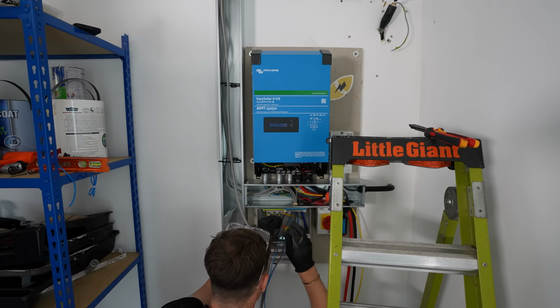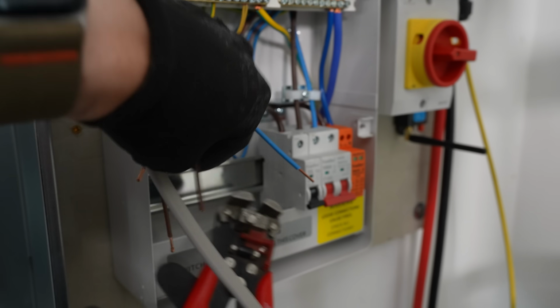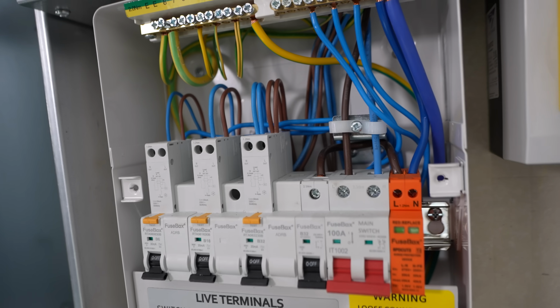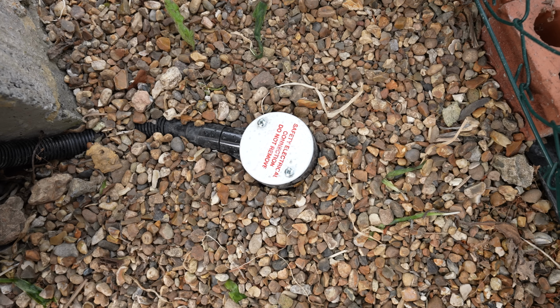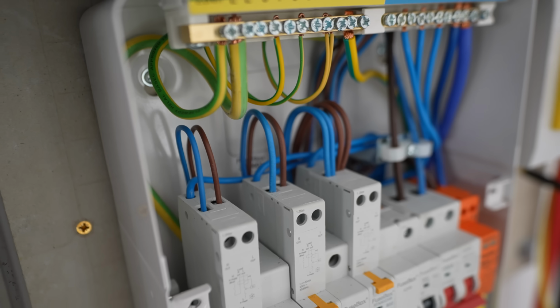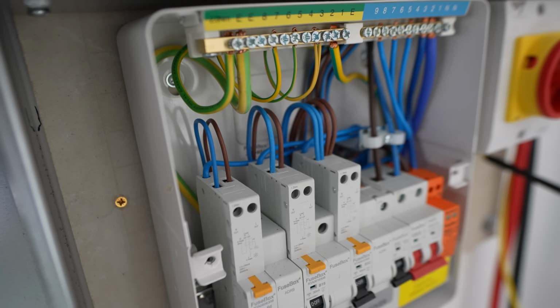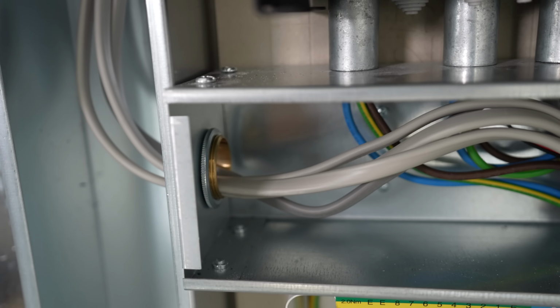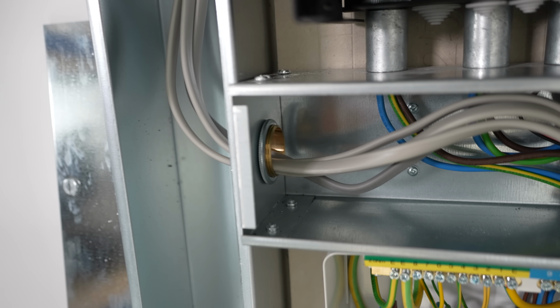Now you'll note we've used an RCBO, a 30 milliamp RCBO, on every circuit. This is because effectively we have an isolated earth here - we're not connected up to any outside system. That means it's technically a TT system, not so common here in the UK but very common in Europe. It's essential that you have 30 milliamp protection on every circuit and double check all of your earthing.